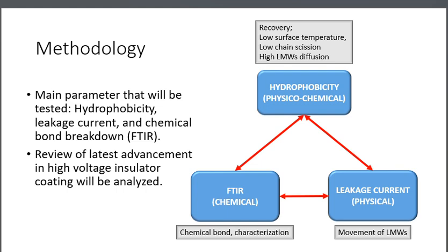3 major parameters were analyzed in the literature. First is hydrophobicity. This property determines the ability of the coating to repel water and prevent the formation of conductive water films. Second, leakage current. The leakage current reflects the electrical performance of the insulator surface condition under contaminated conditions. And the third, chemical bond degradation. This is analyzed using Fourier transform infrared spectroscopy, or FTIR, to study changes in chemical bonds after aging. Together, these parameters provide insights into the physical, chemical, and physico-chemical stability of the coatings.